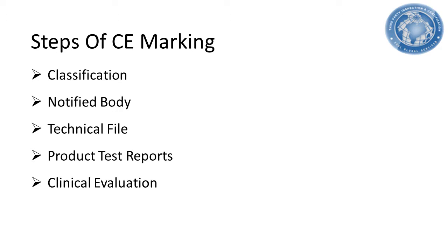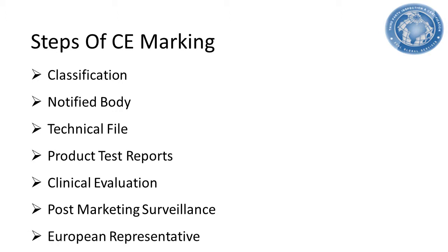The manufacturer is responsible for maintaining updated clinical evaluation records. The manufacturer needs to implement a system of post-marketing surveillance, advisory notices, product recall procedures, etc. For all non-EU country manufacturers, or when you are outside of Europe, you have to appoint a European representative as per the guidelines of the directive.